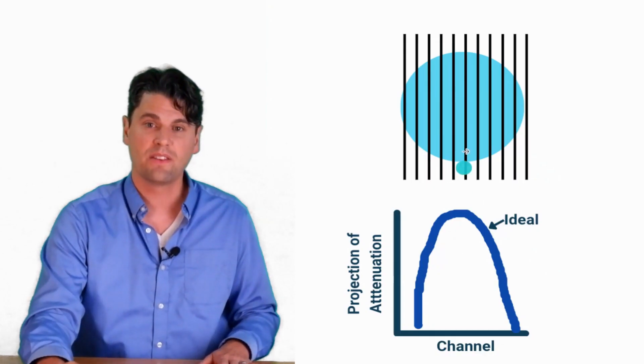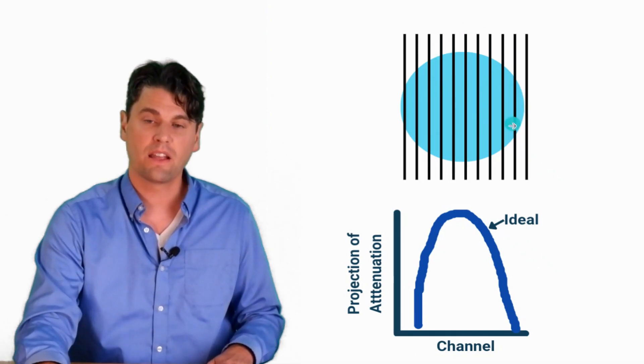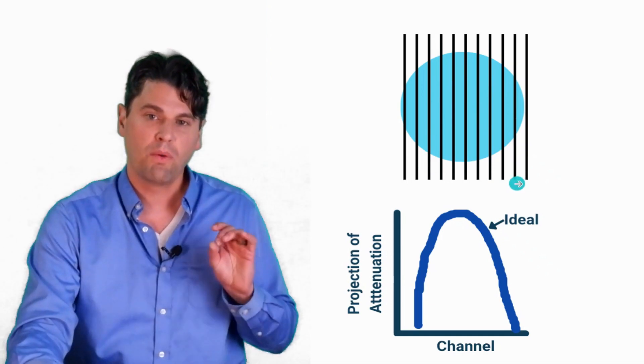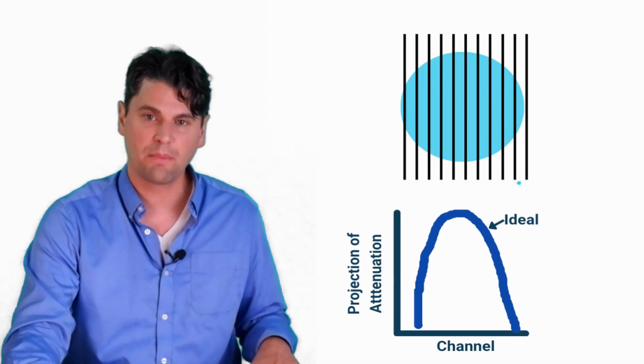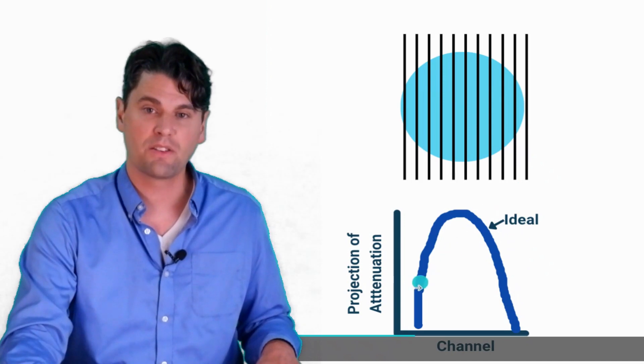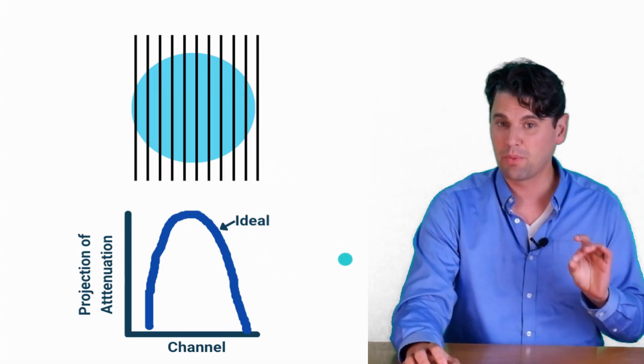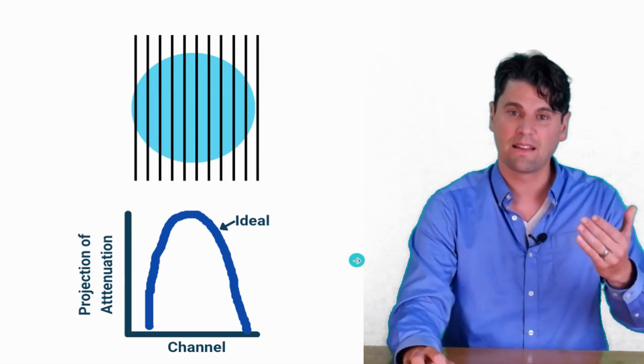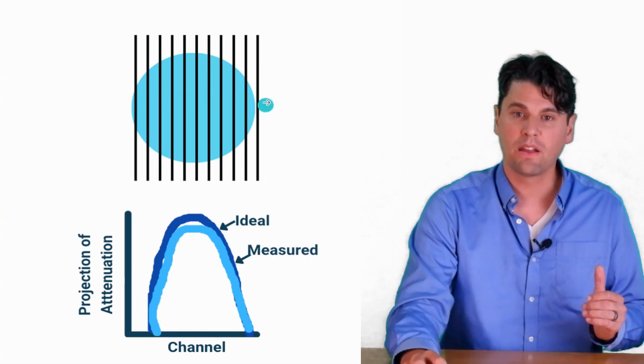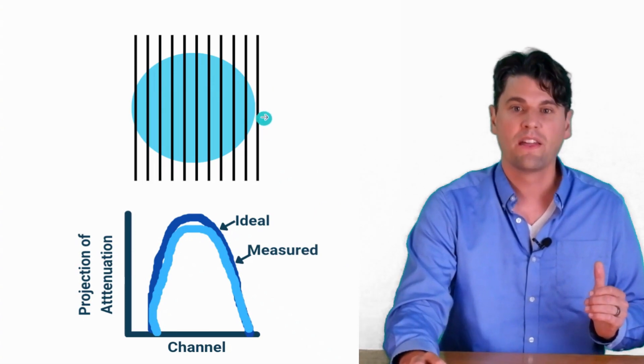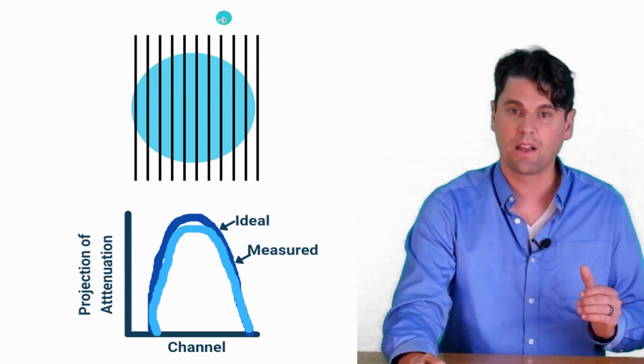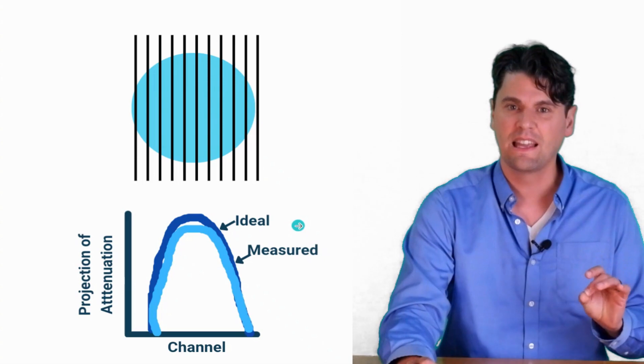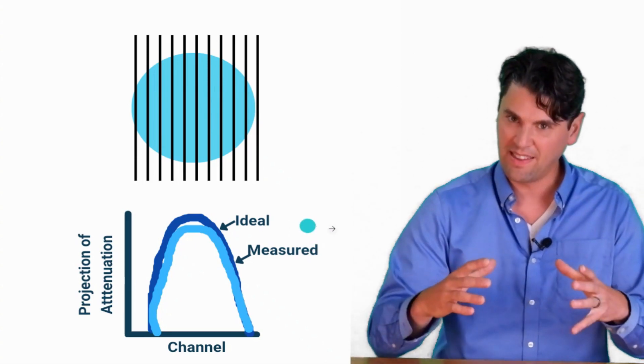As the x-rays pass through the water and get measured on our detector, we take the negative log of the signal to get projection measurements. Ideally these projections would be uniform. But in reality, x-rays that pass through more material get a harder beam, which attenuates a little bit less. The x-rays out at the edges pass through only a little material and aren't hardened much, while x-rays through the center are hardened more. So our measured values are a little short of the ideal values, especially at the long path lengths through the center of this uniform phantom.